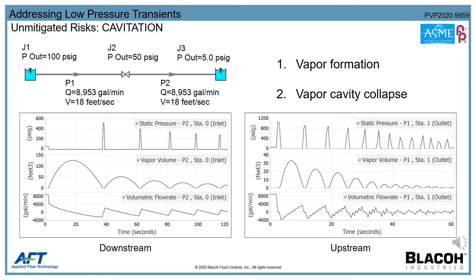Eventually the flow reverses and the vapor pocket collapses, causing the pressure to spike over 500 psi. On the upstream side, a high-pressure transient is immediately initiated, causing the pressure to spike to over 1,000 psi. As the flow oscillates back and forth, the same series of events that immediately occurred on the downstream side now occur on the upstream side, and multiple bursts of pressure ensue until the energy is eventually dampened by friction.